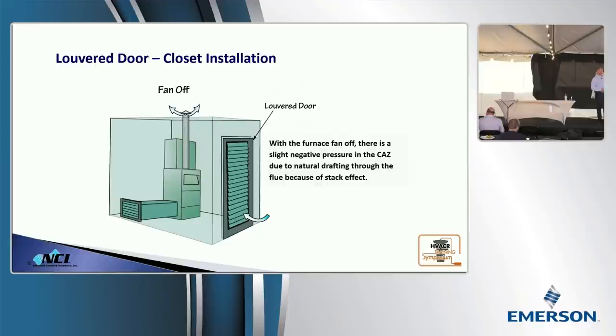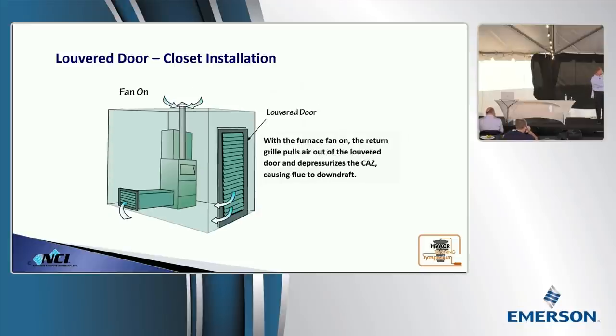So we've got natural air movement. Once the blower kicks on, though, what happens? What do you think is going to happen here, guys? It's a louvered door. Yeah. Path of least resistance. That blower kicks on. We've got a central return. Air will pull backwards through those louvered doors to get to the return out through the draft hood.